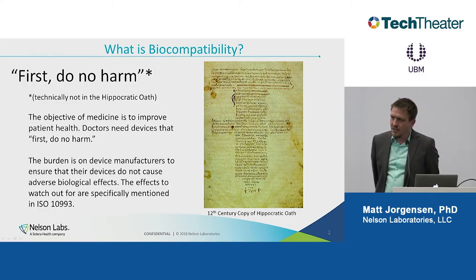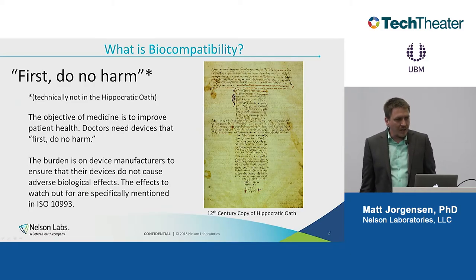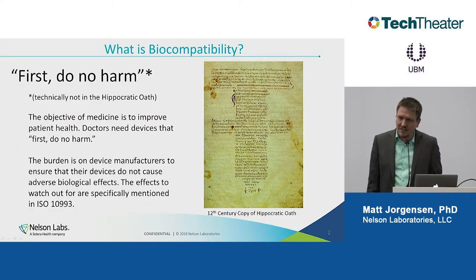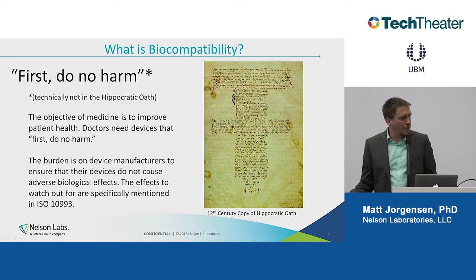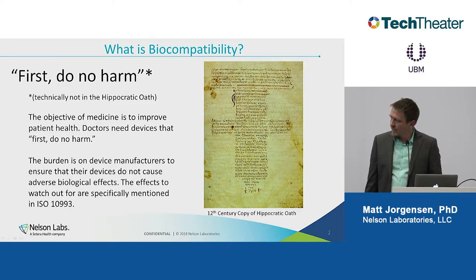When it comes to the specific risks, all the different ways that a device could harm somebody, these are sort of tabulated in the ISO 10993-1 document. And in the U.S., you have the FDA's interpretation of the ISO 10993 document. There's certainly more risks than what's listed there, but those are the ones that the FDA really cares about. So our job is to prove that the device doesn't result in those effects.